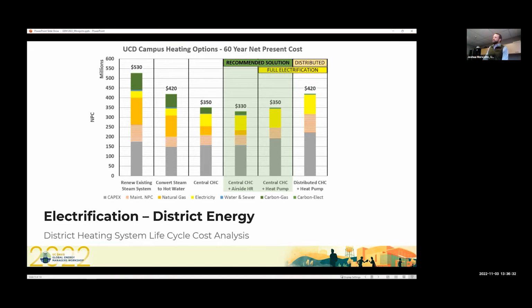The challenge for us, with an existing campus the size we are, is the number of heat pumps, the electrical infrastructure that would be needed at the building level to support that, and the maintenance required for that much new equipment on campus.